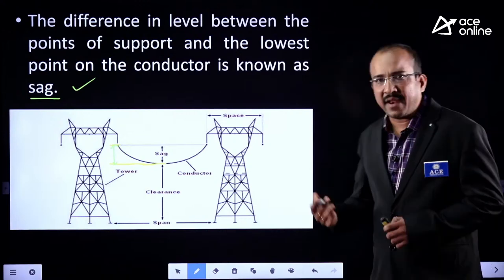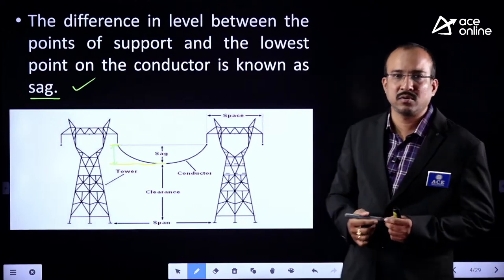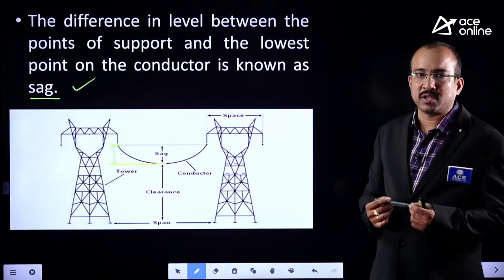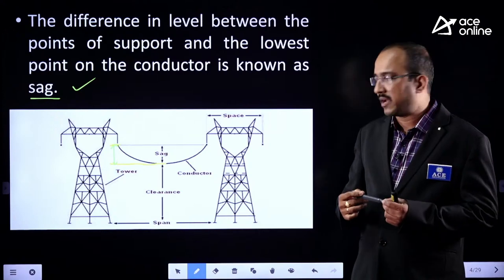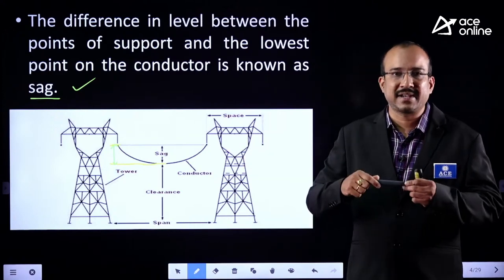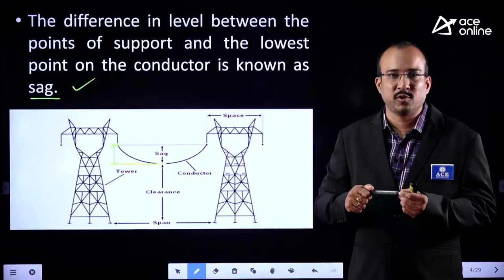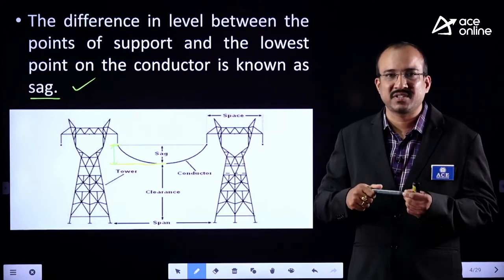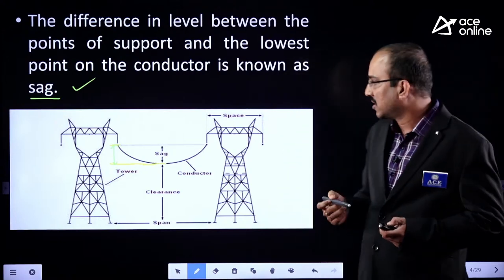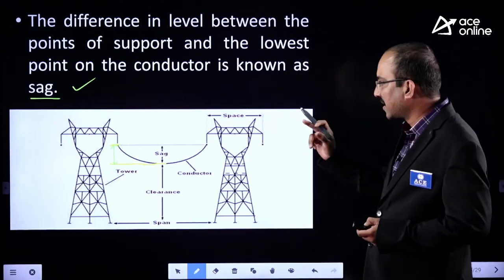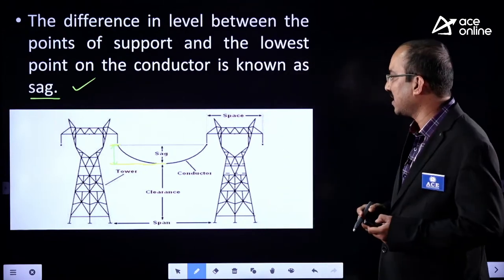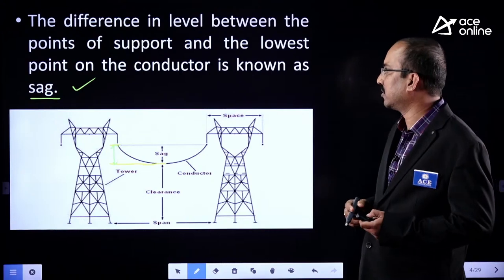Can we make the SAG zero? No. Because if you make the SAG zero, the conductor will experience more tensile stress and it may break down. That is why permissible SAG is to be allowed.